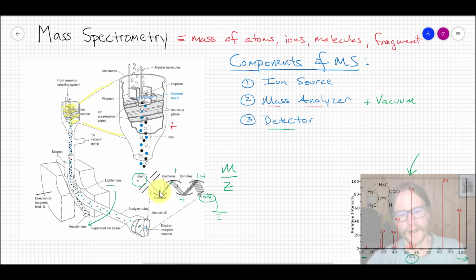Usually we measure the current here, and then we convert that current into a voltage, and that scales. But this can give us roughly 10 to the 5th, 10 to the 6th sort of amplification from our original ion. So one ion maybe gives us 1,000,000 electrons, and we measure that as current. That's how many instrument detectors work. Of course, there's 1,000,000 different versions of this, and the electronics all change. But this sort of cascading effect is a pretty common one because it has built-in amplification.